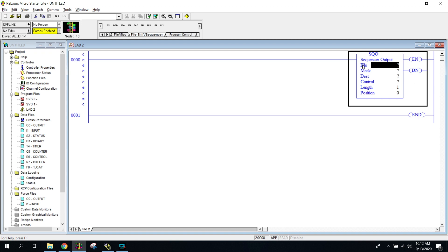The first thing we're going to need to know is the file. How a sequencer works is it steps through a bunch of different files, looks at each file, and turns bits on. We're going to look at a word and determine what bits are going to be turned on, and it's going to write that to a destination. The file we're going to be looking at for the information is going to be our N7, so we'll type in N7 colon zero.